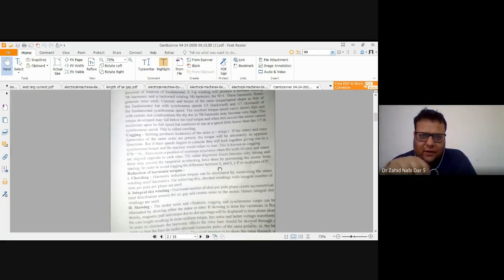For example, it is 5. The other thing should not be equal to a multiple; it can be equal to 11, it can be equal to 13, because by an integer multiple of 5 you will not get 13. If you multiply any integer with 5, you should not get that value. Then only there would be no cogging phenomena.